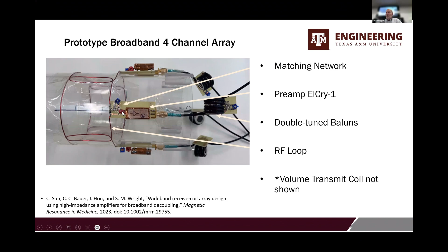And we built a phantom with deuterium, sodium, and proton, different concentrations, and then used the same array, no tuning at all, just the same array at these 3 different frequencies, and made array images at all of them. I'm hurrying through this, but signal noise, there's a little signal to noise loss. Less at sodium than at deuterium, but it's pretty good comparing to a conventional isolation preamp where you would have to have separate preamps for different frequencies. This is just the same preamp working at the same frequencies.